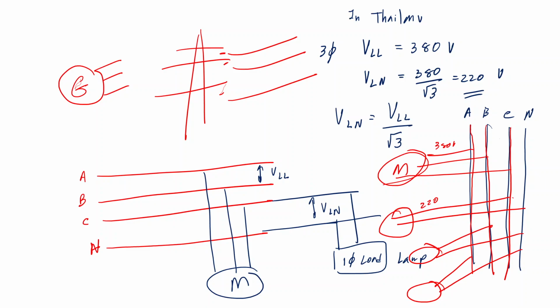Okay. So you can see the switch panel, the breaker panel, right? It has three phase, the switch of single phase. And the designer will design the system to balance every phase, to use every phase equally. We try to use phase A, phase B, and phase C in equal condition, as much as possible. Okay, you get some idea about the three-phase system, right? In a three-phase system, the voltage is higher than single-phase system because we use line-to-line voltage.